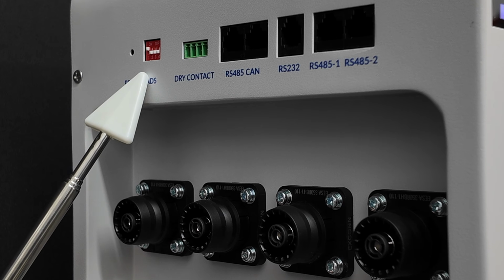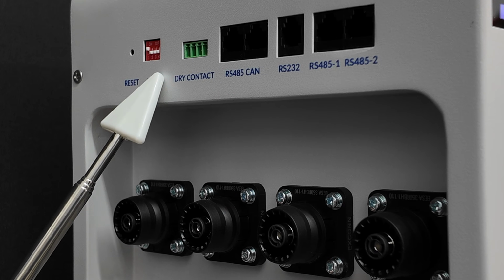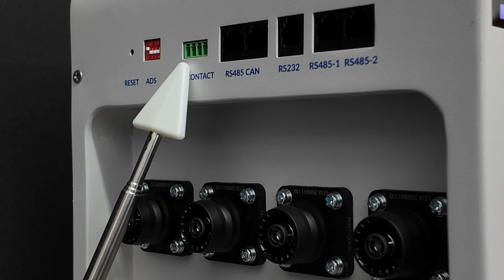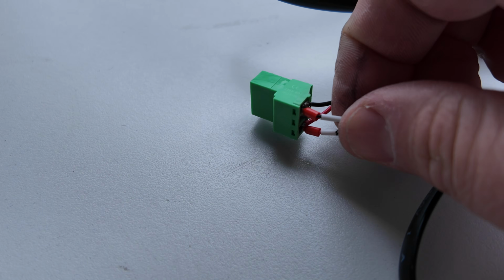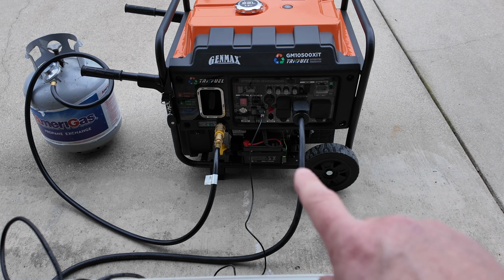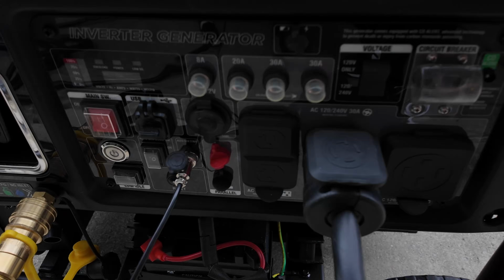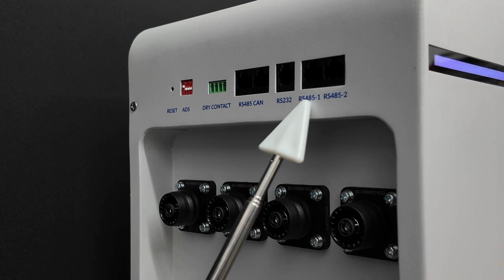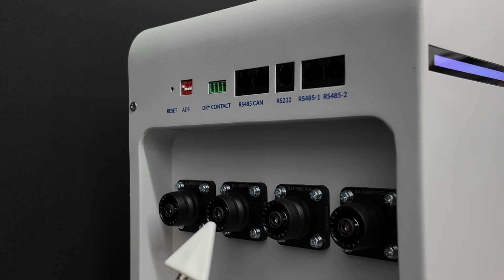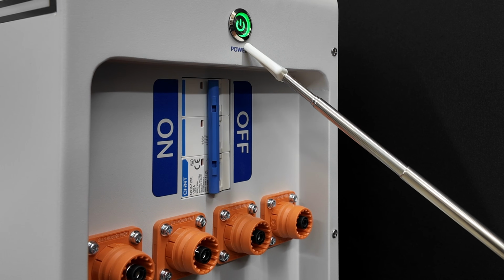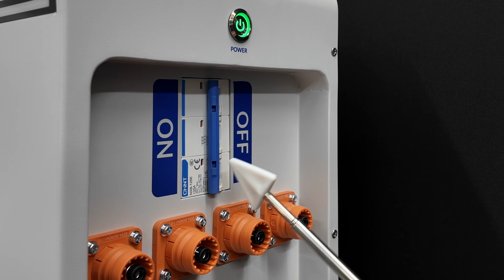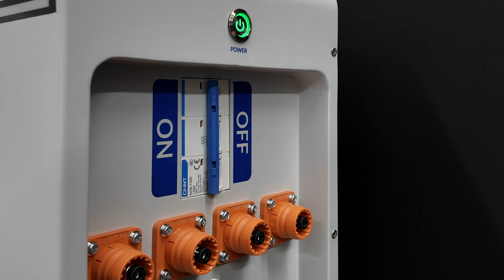You also have your address switch for battery number 1, 2, 3, or 4, and also dry contacts, which means you can hook this up to, say, a 2-wire start generator, and it can start it depending on the amount of voltage or the state of charge. You have all your communication ports up here, and then your battery terminals, which you can also parallel. At the top we have a push button for power, and then our main breaker along with the positive terminals.